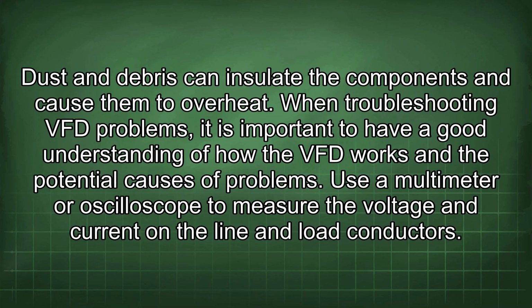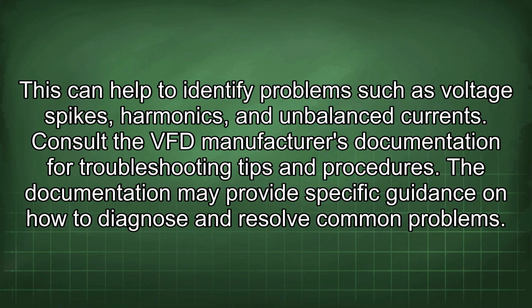When troubleshooting VFD problems, it is important to have a good understanding of how the VFD works and the potential causes of problems. Use a multimeter or oscilloscope to measure the voltage and current on the line and load conductors. This can help to identify problems such as voltage spikes, harmonics, and unbalanced currents. Consult the VFD manufacturer's documentation for troubleshooting tips and procedures. The documentation may provide specific guidance on how to diagnose and resolve common problems.